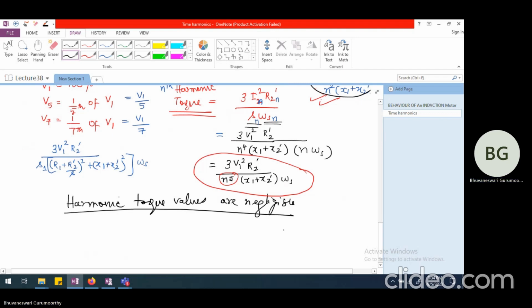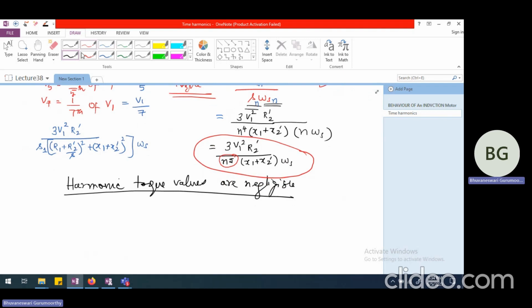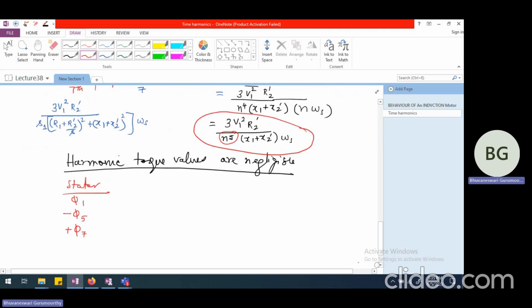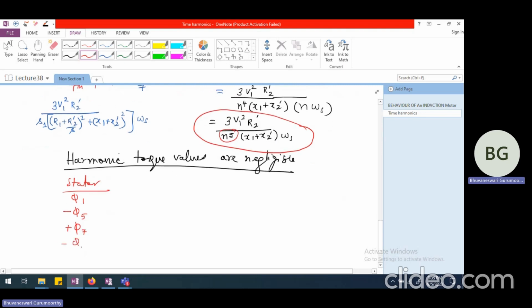But what is really going to create trouble is this. Let us say on the stator side, I have flux corresponding to the fundamental component, flux corresponding to the fifth harmonic, flux corresponding to the seventh harmonic. This is rotating in the negative direction, whereas this is rotating in the positive direction. Similarly, I'm going to have flux corresponding to the 11th harmonic, which is rotating in the reverse direction, and flux corresponding to the 13th harmonic, which is rotating in the positive direction. Now, these are going to induce current in the rotor.